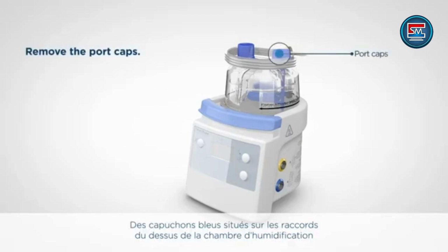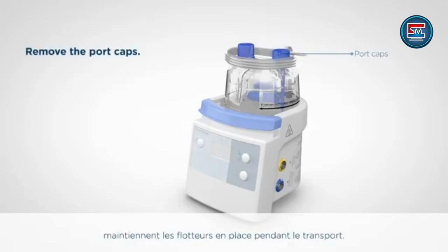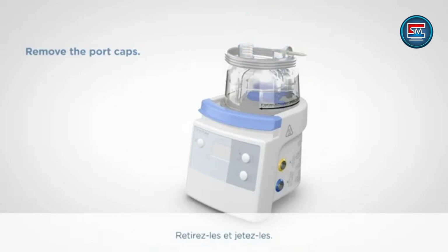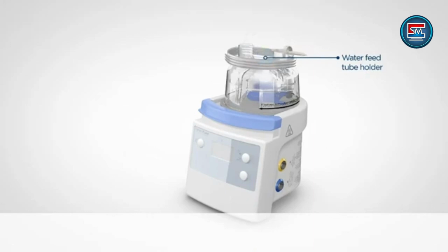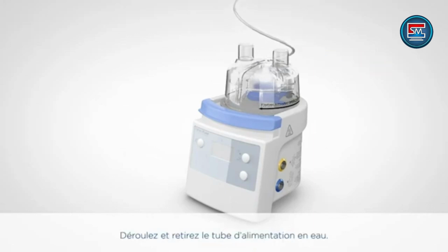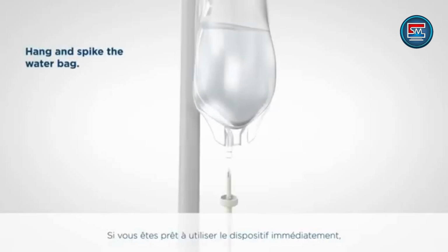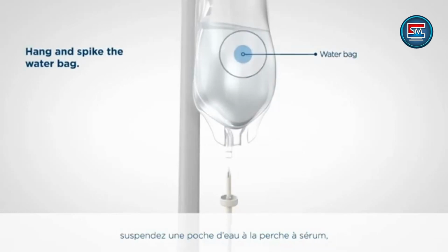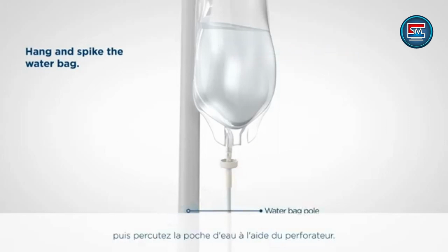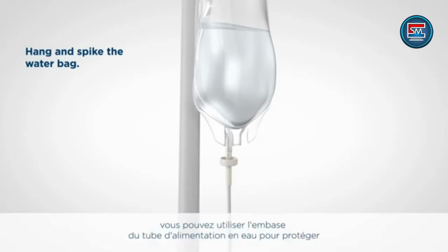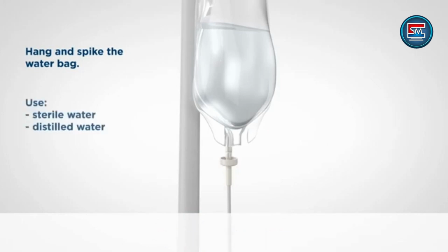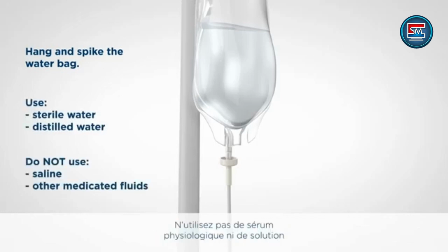There are blue port caps on the top of the chamber that hold the floats in place during transport. Pull up on the ring attached to these port caps, remove and discard them. Under the port caps, there is a water feed tube holder. Unwind and remove the water feed tube. If you're ready to use the system immediately, hang a water bag on the water bag pole and spike the water bag. If you are setting up for future use, the water feed set holder can be used to protect and keep the water bag spike clean. Use sterile or distilled water. Do not use saline or any medicated fluid such as glucose.